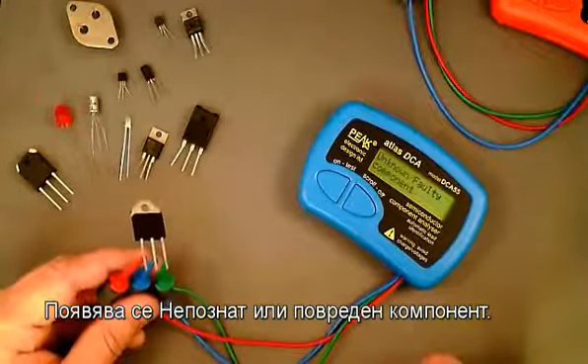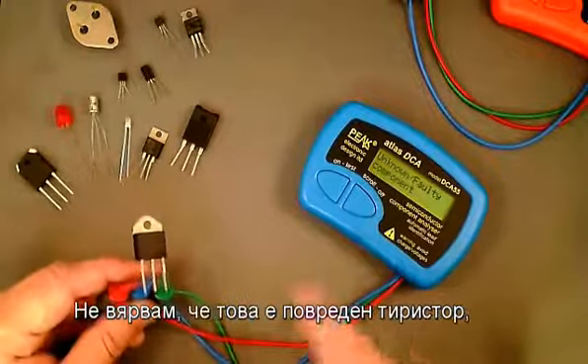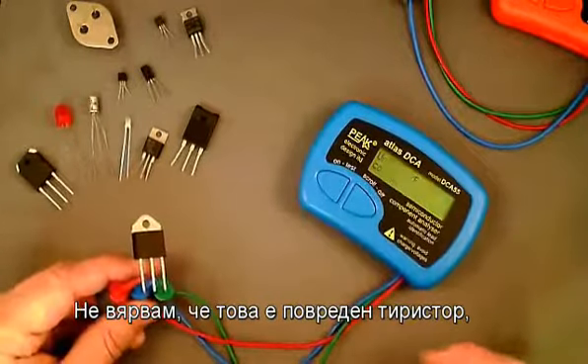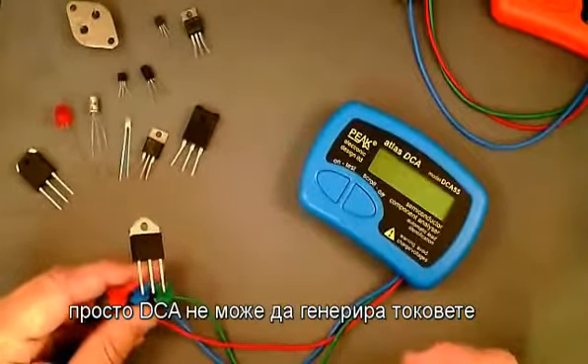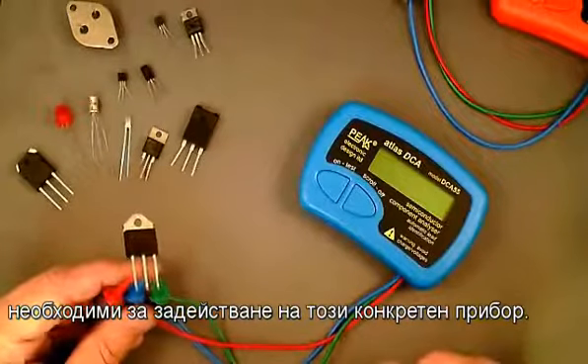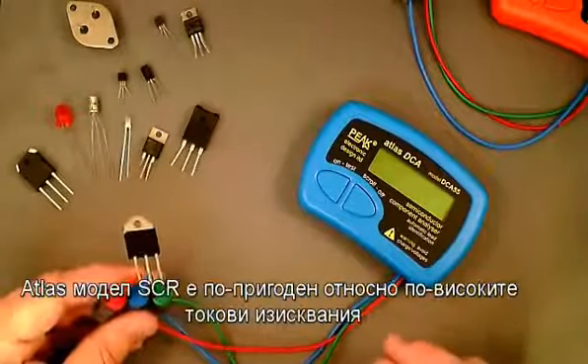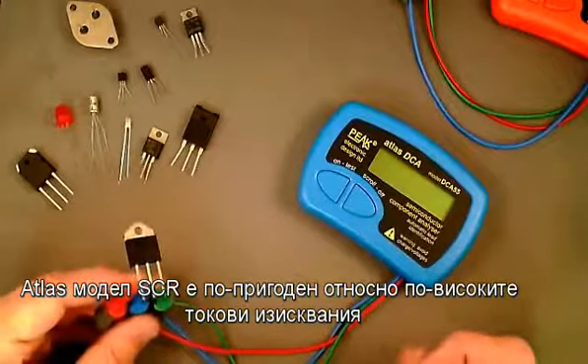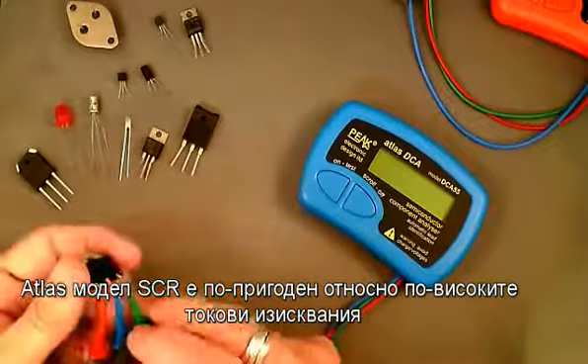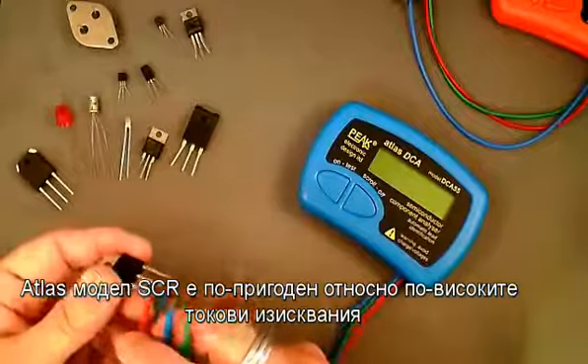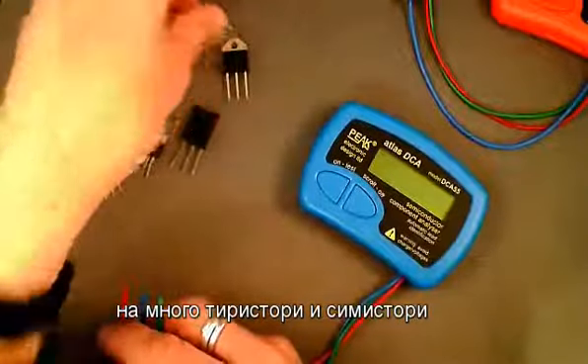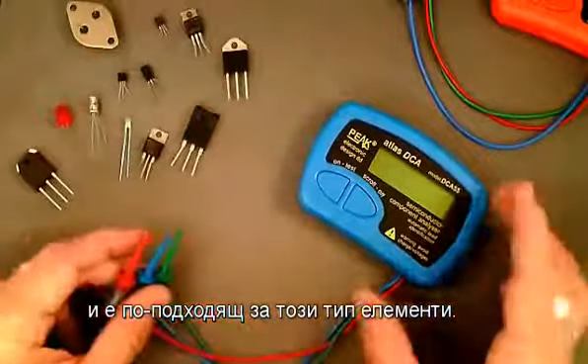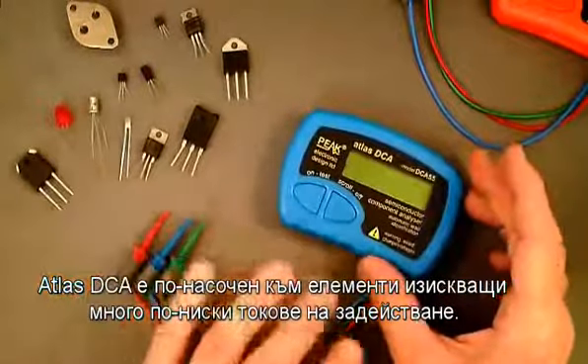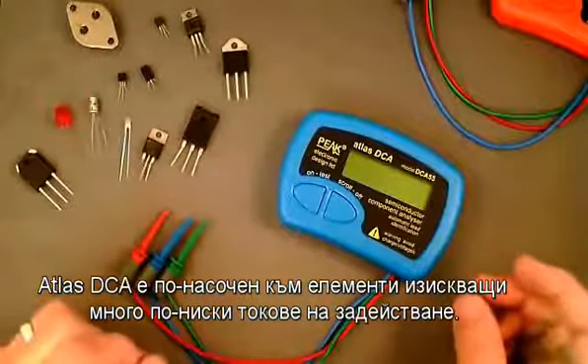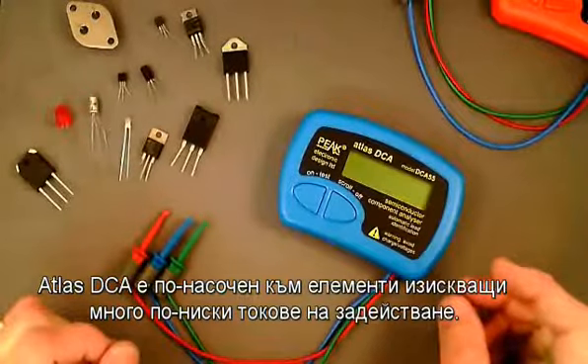Here it's come up with unknown or faulty component. I don't believe this is a faulty thyristor. It's just that the DCA is unable to generate the currents required to trigger this particular part. The Atlas SCR product is more geared towards the higher current requirements of many thyristors and triacs, and that is suitable for those sorts of parts. The Atlas DCA is more suitable for parts that require much lower currents to trigger.